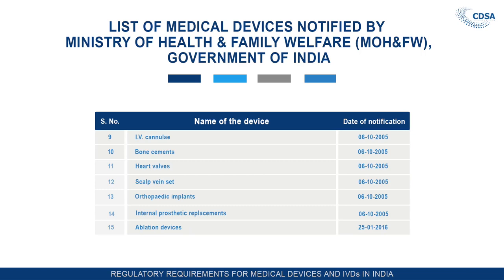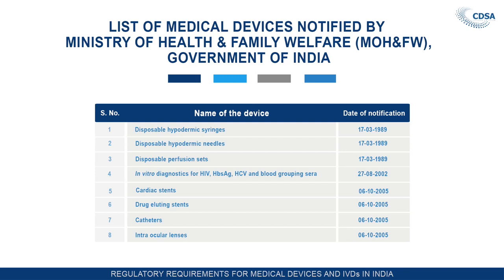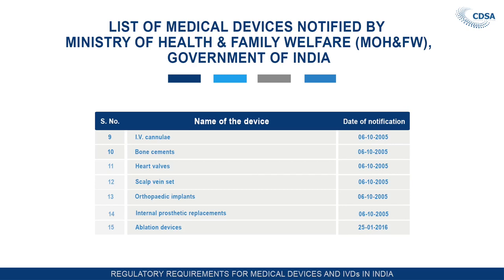In 2005, the Ministry of Health and Family Welfare notified 10 additional medical devices under Section 3(b)(4): cardiac stent, drug-eluting stent, catheters, intraocular lenses, IV cannula, bone cement, heart valves, scalp vein set, orthopedic implants, and internal prosthetic replacements. In 2016, ablation medical devices were notified. As of that point, a total of 15 categories of medical devices had been notified under the Drugs and Cosmetics Act and were under regulation.